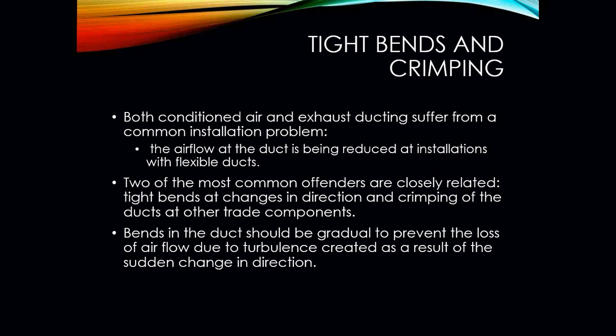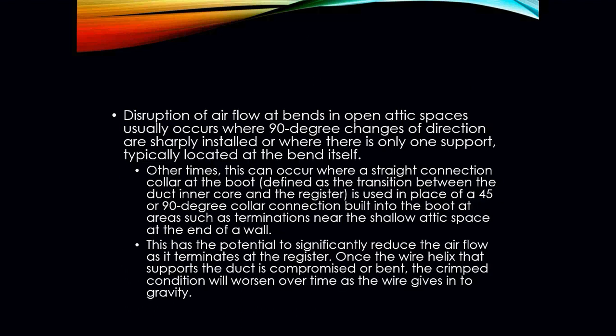Okay, bends in the duct should be gradual to prevent the loss of airflow due to turbulence created as the result of sudden change in direction. Okay, disruption of airflow at bends in open attic spaces usually occurs where those 90-degree changes of direction are taking place. Okay, these sharp changes in direction typically have only one support located at the bend itself. Other times it can occur with a straight connection or collar at the boot, which is defined as the transition between the duct inner core and the register, and is used in place of a 45 or a 90-degree collar connection built into the boot at an area such as terminations near the shallow attic space or at the end of a wall.